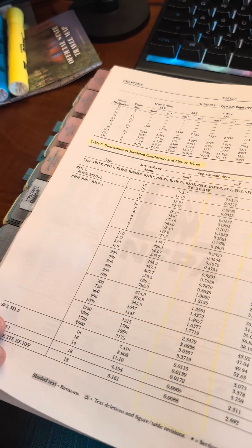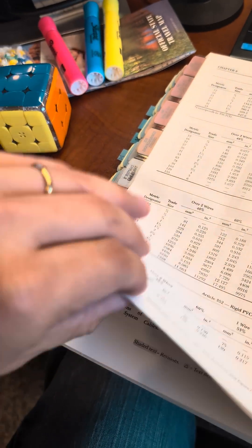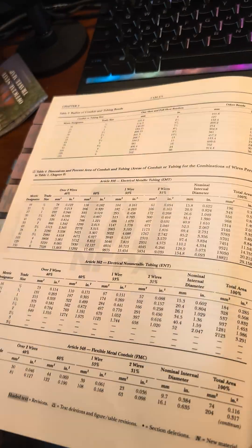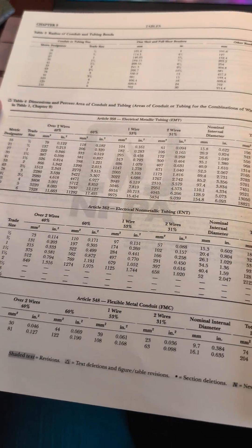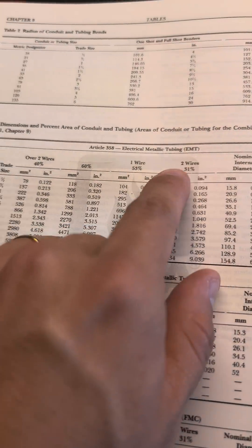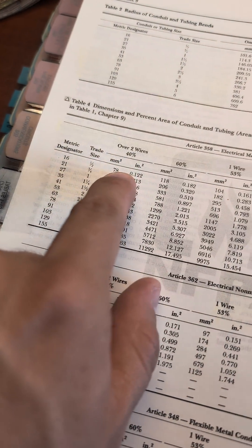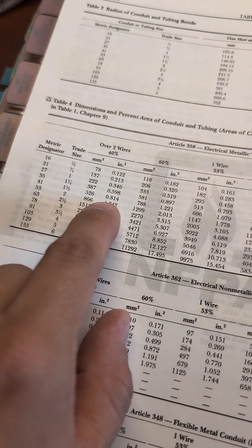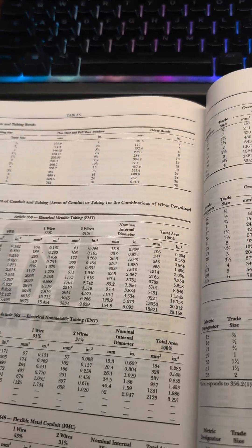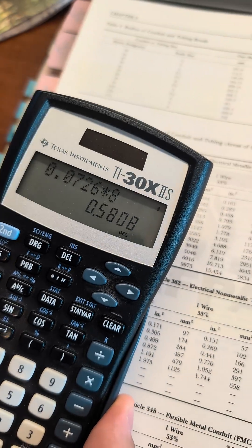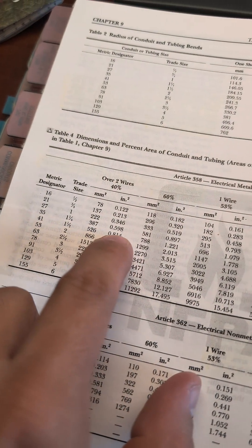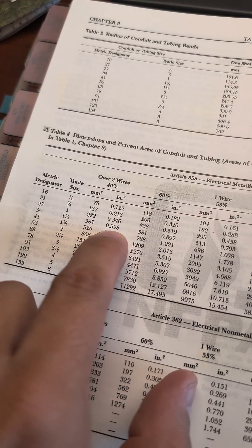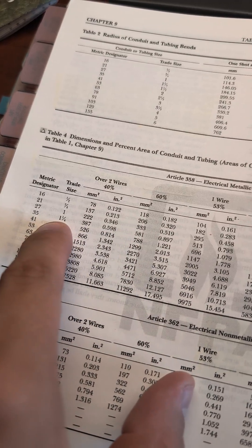Now we can go from Table 5 to Table 4 — the Dimensions and Percent Fill. We're going to be looking for EMT, and since we're over 2 wires, it's 40%. Looking at our calculator, we need 0.58. We have 0.598 available, so the answer is inch and a quarter.